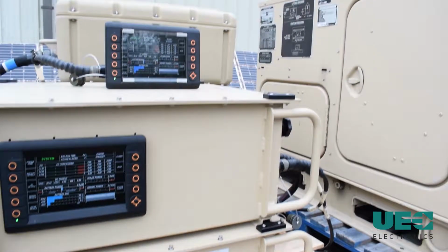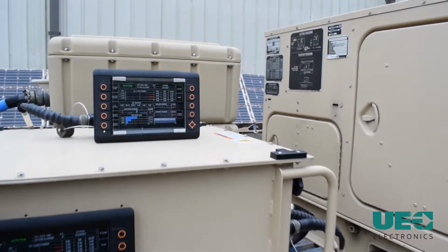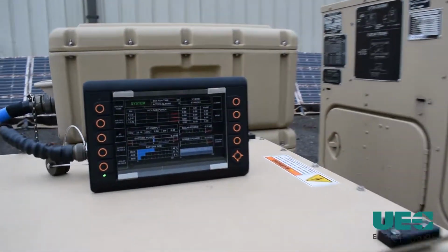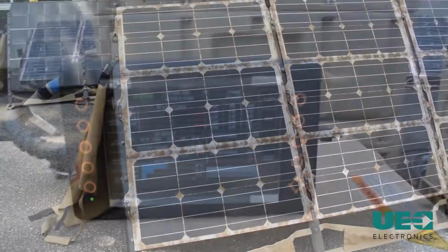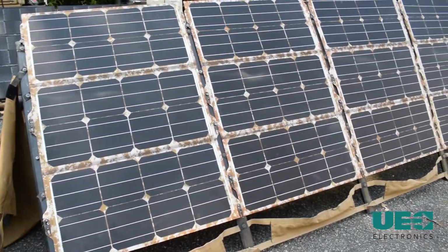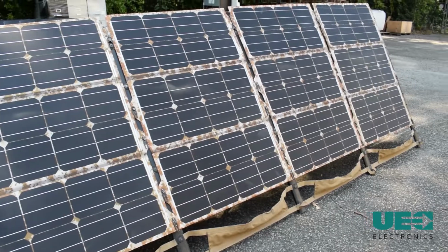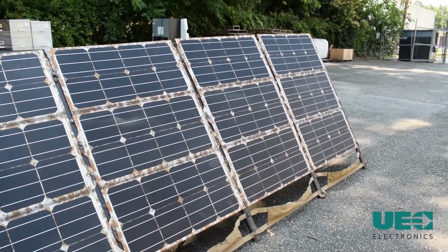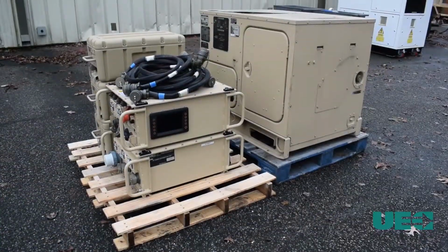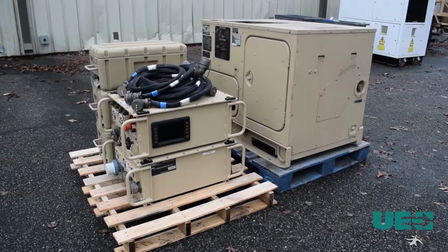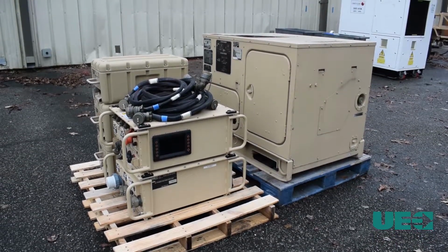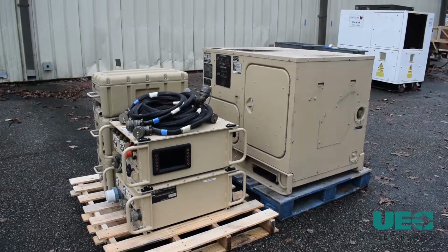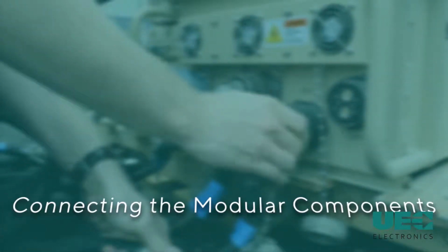If it will be used, locate the system within 15 feet of the location where the remote HMI will be displayed. The solar interface cables are 30 feet in length, so the system should be located within 20 feet of the solar array. The generator interface cable is 15 feet in length. Locate the PDU within 10 feet of the generator.